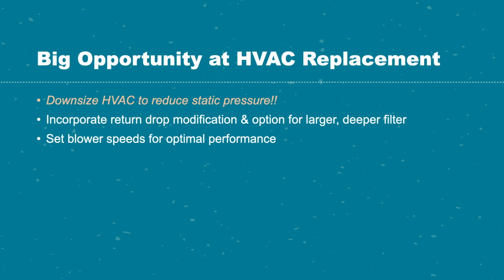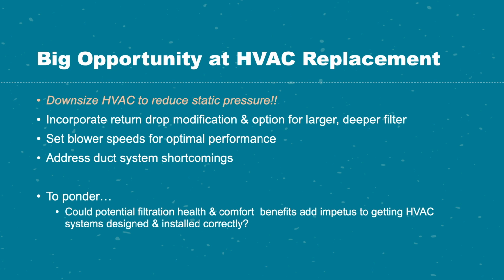Ideally, when it's installed, it should be installed right. You should request that you make sure that you check and set the blower speeds and check the static and all those things. When you replace a system, a good HVAC contractor should address any shortcomings in your duct system. And it seems like the combination of health and efficiency and performance could really allow good HVAC contractors who want to do it right rather than just be low bid to compete more effectively if people were more aware of what they're losing when they go with HVAC low bid.